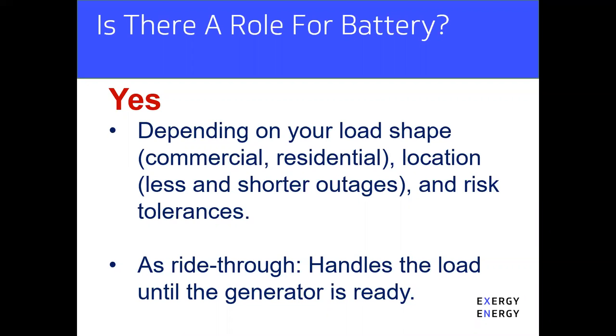So John, if I need to size a battery for essentially ride-through, how quickly does a Cummins natural gas generator go from a cold start to being able to handle full load? Yeah, sure. In that application, usually there's a little bit of a delay to make sure there's an actual outage—a couple seconds, maybe 3, where you purposely don't start the generator so you can ensure it's a true outage. Then you give it a start command, and within about 7 seconds it's ready to accept load.